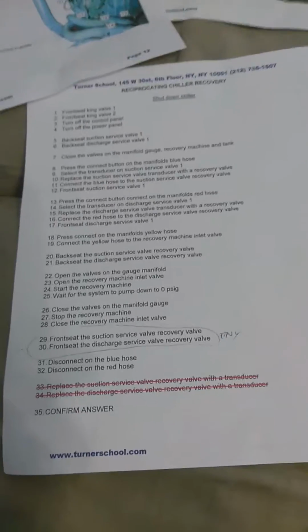Stop the recovery. Close the recovery machine inlet valve. Front seat the suction service recovery valve. Front seat the discharge service recovery valve. Disconnect the blue hose. Disconnect the red hose.